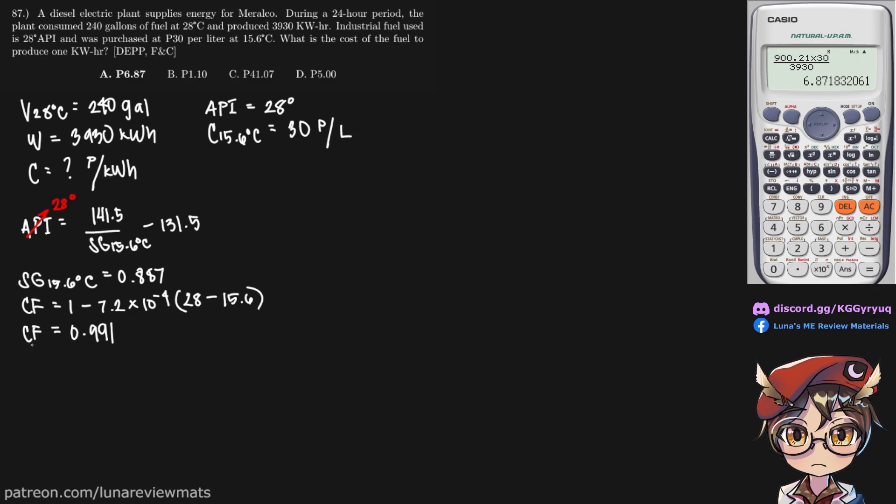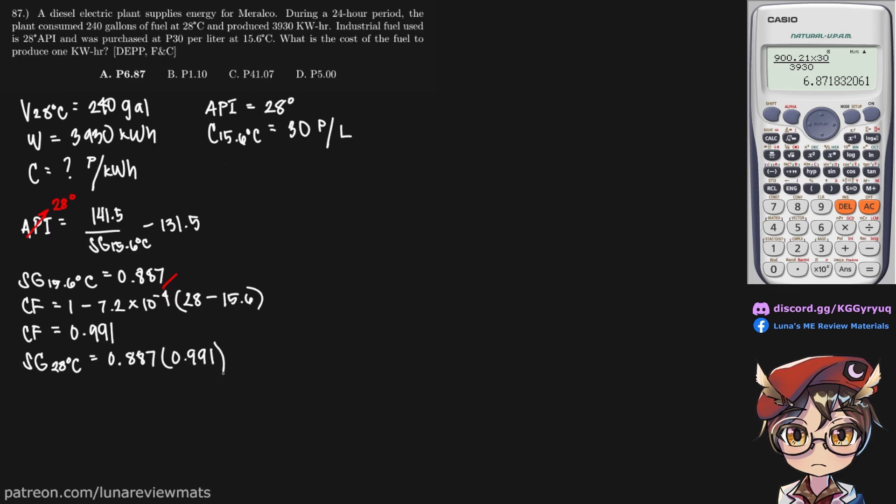And now we can get the specific gravity of our fuel at 28 degrees C. So that is simply 0.887 multiplied by our correction factor, and we should arrive at a value of 0.879.